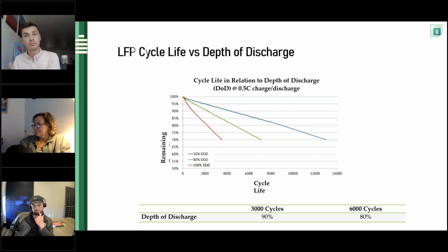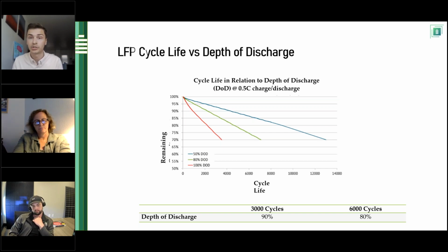You can use more of your battery, i.e. 90% depth of discharge. If you look at that red line, that's 100%. But somewhere in between that green and that red is where 90% is going to lay, right? And you'll see that you're getting more usable power, but the trade-off, because there's no such thing as a free lunch, is that you're going to get fewer life cycles.